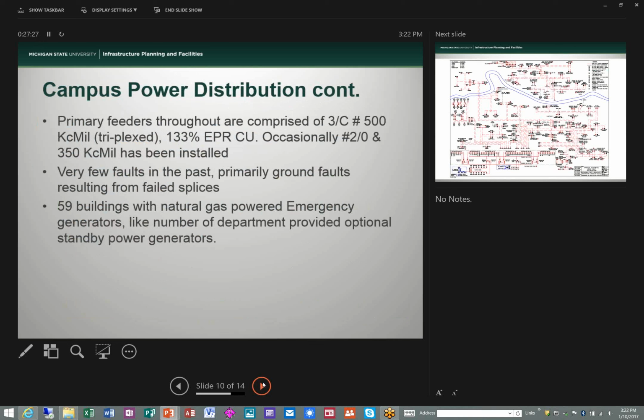Unlike some of the other presentations in the past, we have very, very few faults here on campus. Talking with the director of our field installation crews, I can't remember a time we've had a bolted fault or a phase-to-phase fault, with the exception of a squirrel that got into a cabinet. Aside from that, the occasional failed splice, we'll get a single line to ground fault, averaging between 1,000 and 1,200 amps on the last 2 or 3 we measured, plus or minus.